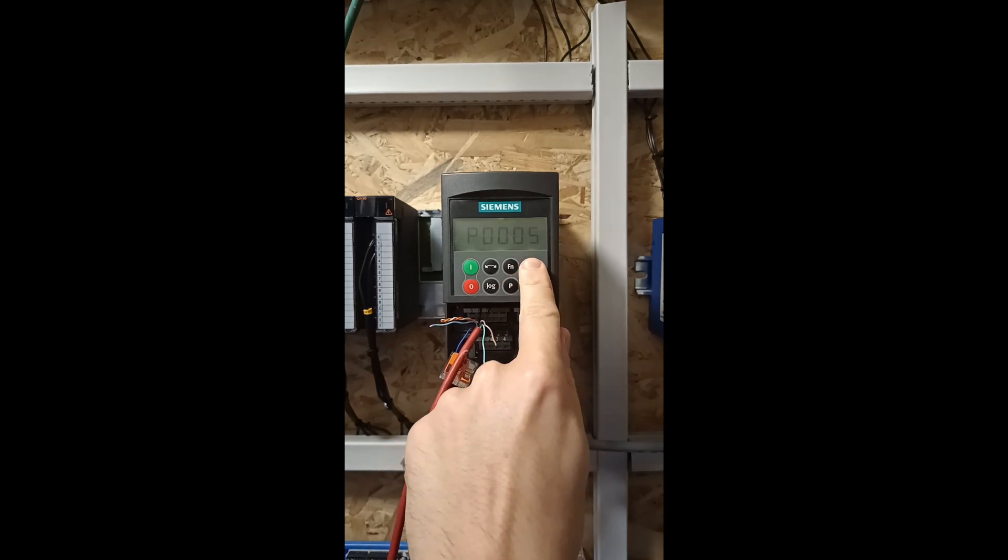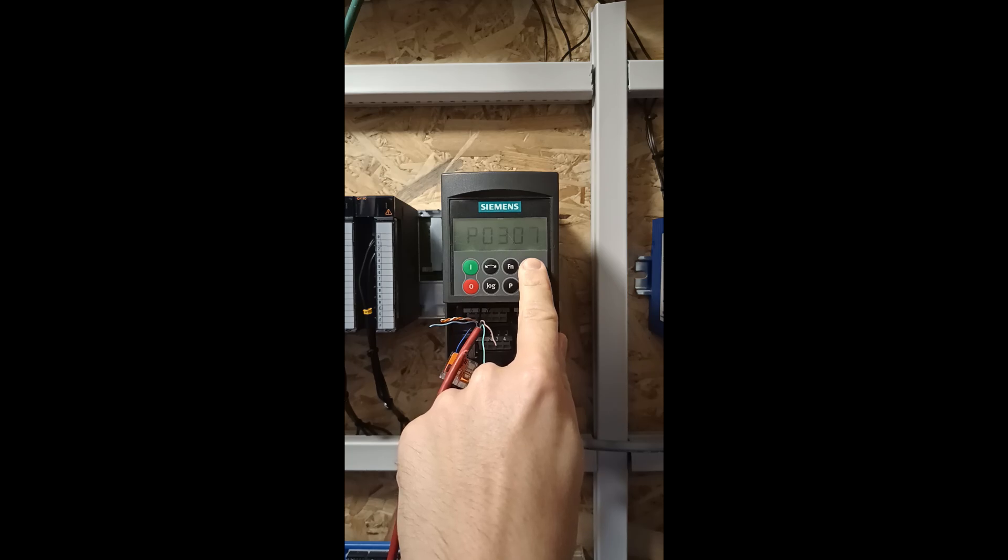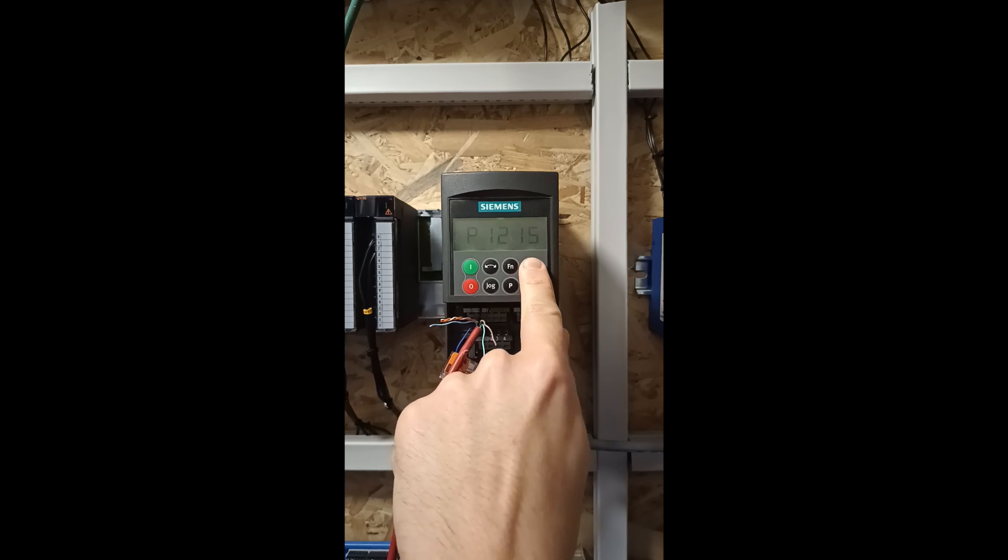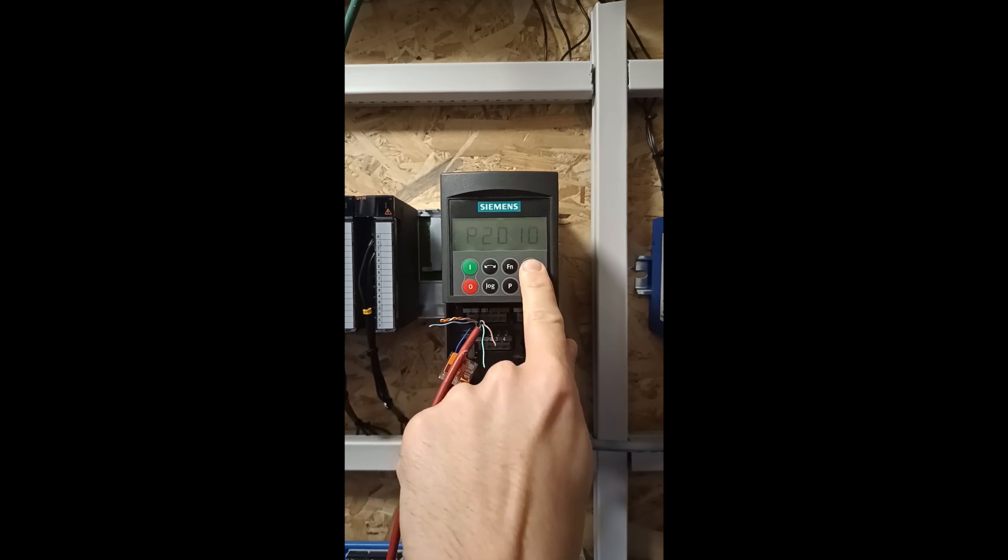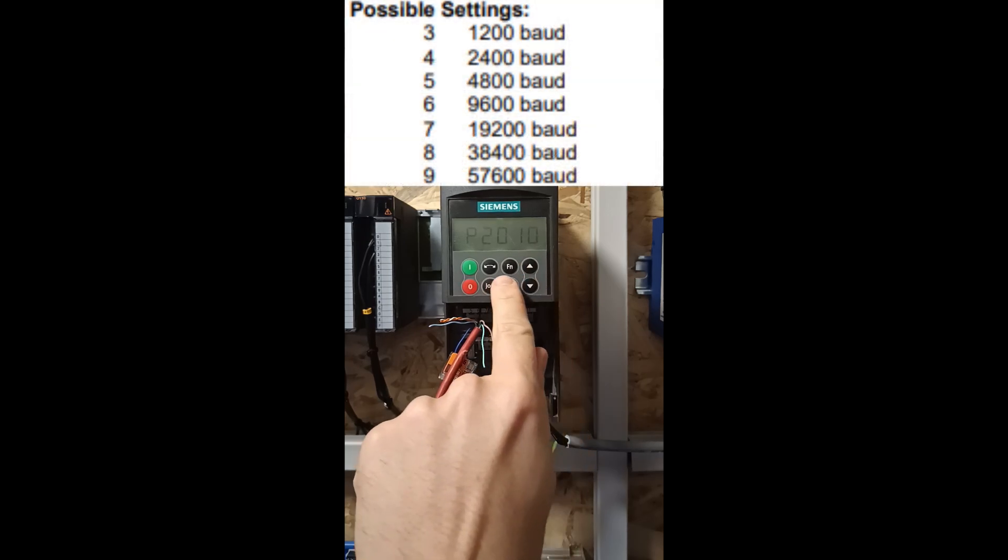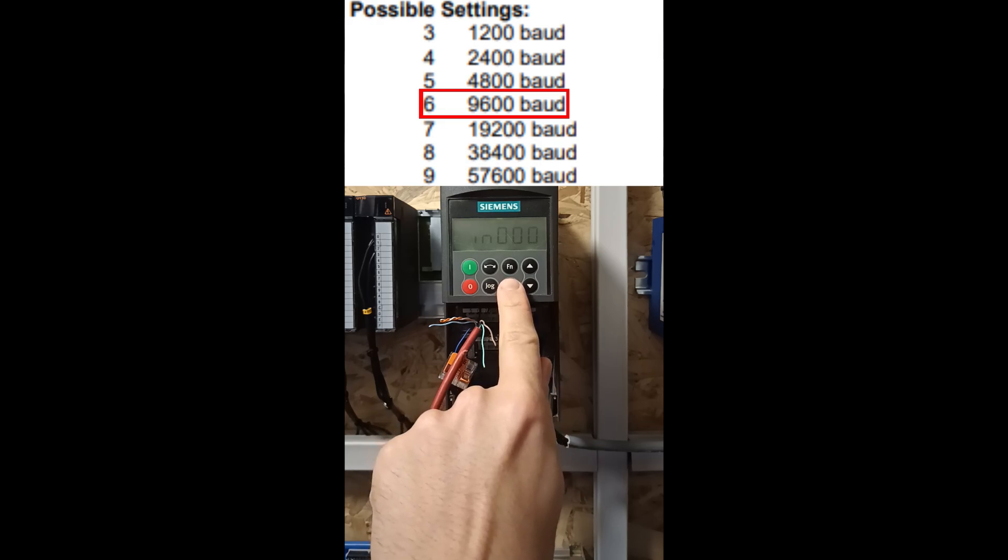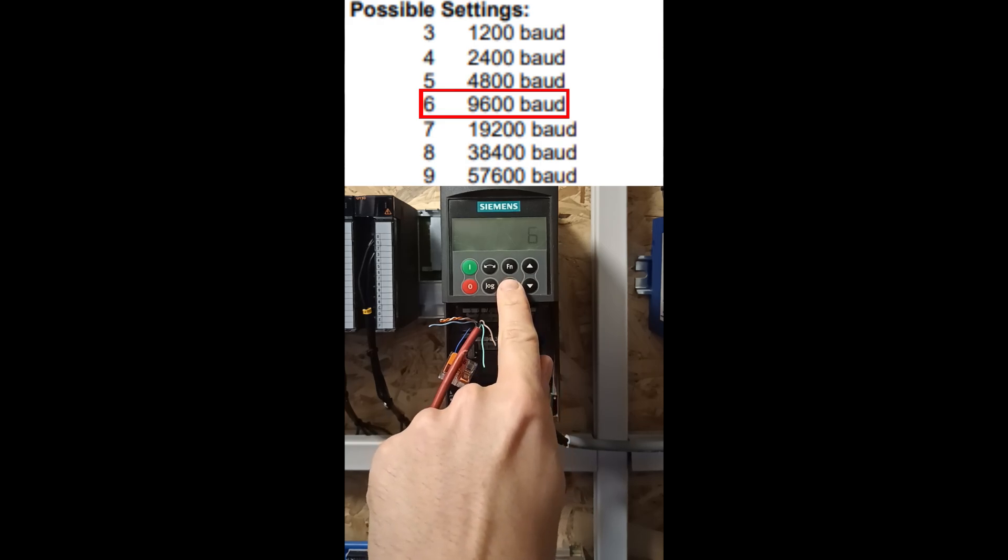Then we want to go to parameter 2010. Here we want to set it to 6. This will set the baud rate to 9600.